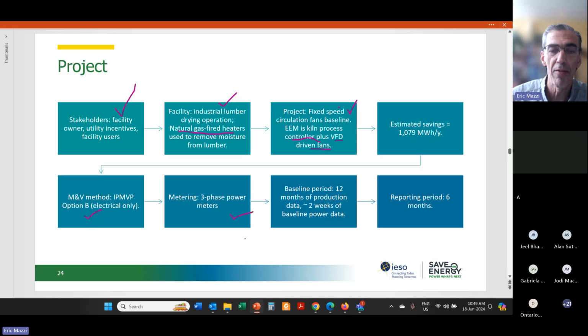We used 3-phase power meters. We ended up with a baseline period of 12 months of production, but we only had about 2 weeks of baseline power data. And then we ended up going with a 6-month reporting period. I'll just mention why only 2 weeks of baseline power data. Well, this is one of the real world logistical issues with M&V: once a project gets approved and some equipment needs to be installed during a shutdown, sometimes there's a really short time period.